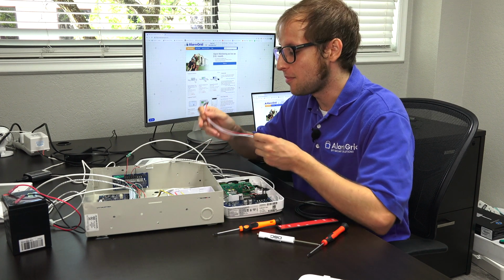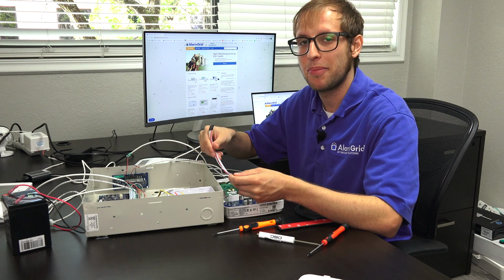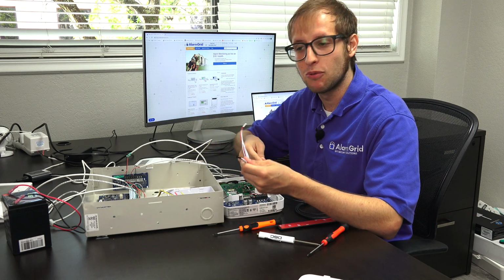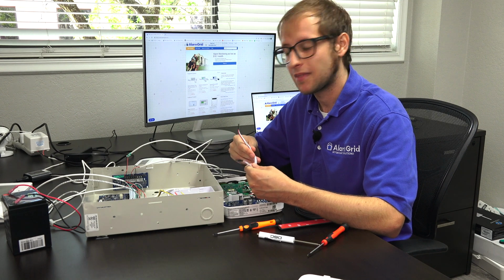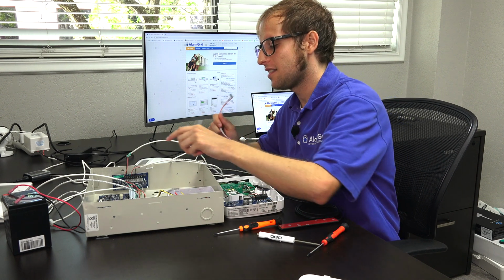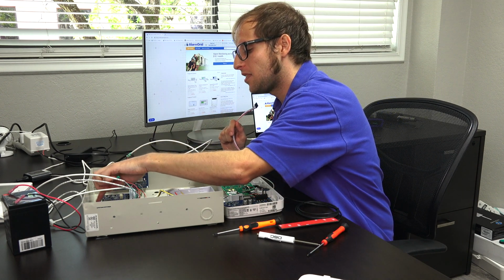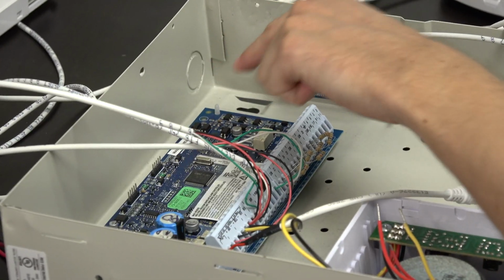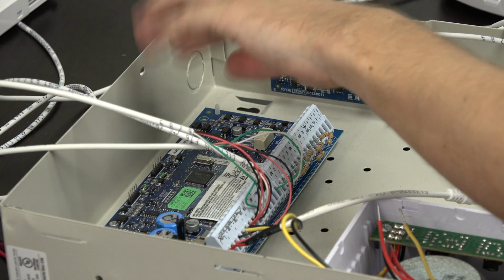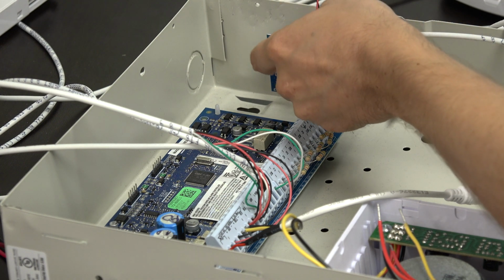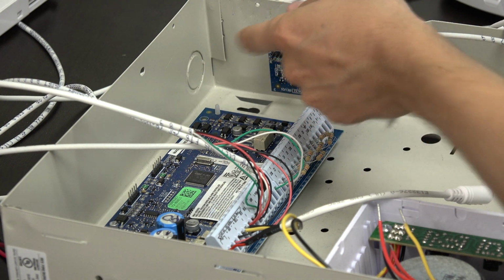So now that we have our six connections made between the communicator and the PCL422, the last thing we need to do is connect the PCL422 to the actual NEO panel using the PC link cable, which comes included with the communicator, as does the PCL422. And so we're going to be using the second PC link connection on the NEO panel. We're not using number one over there. We're using the second one. And we're going to be connecting it to the connection on the PCL422.